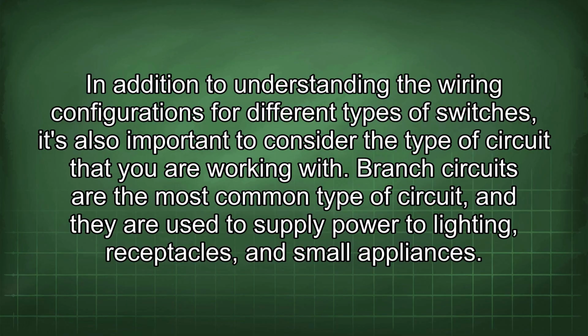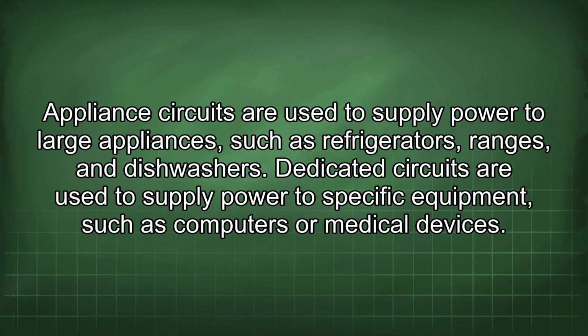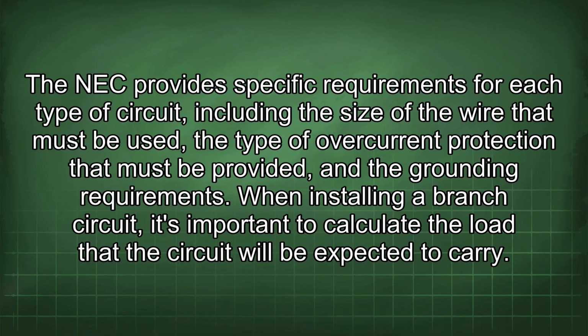Branch circuits are the most common type of circuit, and they are used to supply power to lighting, receptacles, and small appliances. Appliance circuits are used to supply power to large appliances such as refrigerators, ranges, and dishwashers. Dedicated circuits are used to supply power to specific equipment such as computers or medical devices. The NEC provides specific requirements for each type of circuit, including the size of the wire that must be used, the type of overcurrent protection that must be provided, and the grounding requirements.